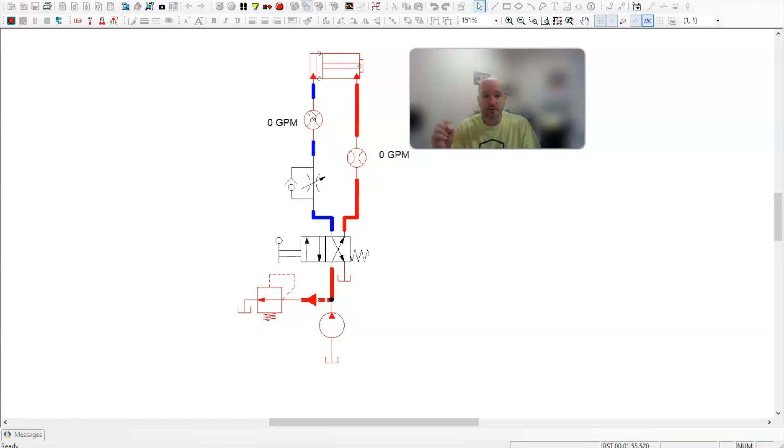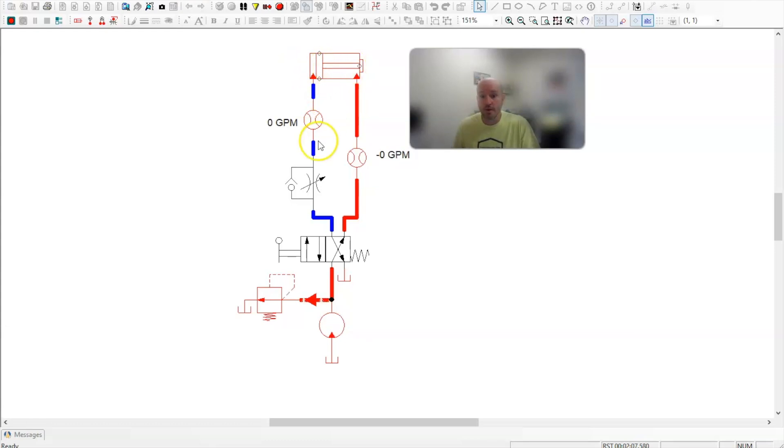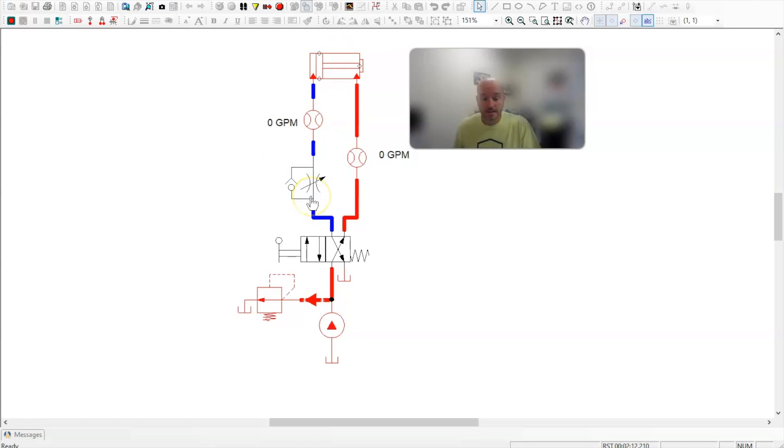So a couple things to look for. One, am I extending the cylinder when it's going slow or retracting the cylinder when it's going slow? Or is it being metered and restricted in both directions? In this case, it's only being restricted in one direction. That's on the extension. My flow control valve is attached to the A port when it's extending.